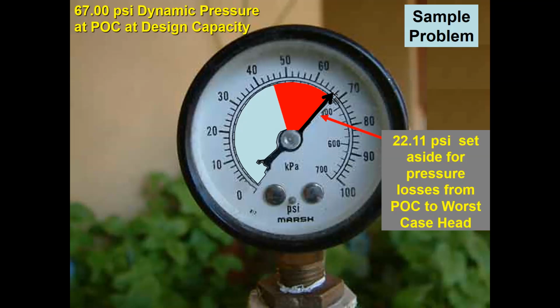We lost that 22.11 PSI due to those components in that system. Again, the piping, the connections, any valves, we lost a whole 1/3 of our pressure. So now we're down to that 44.89 PSI.